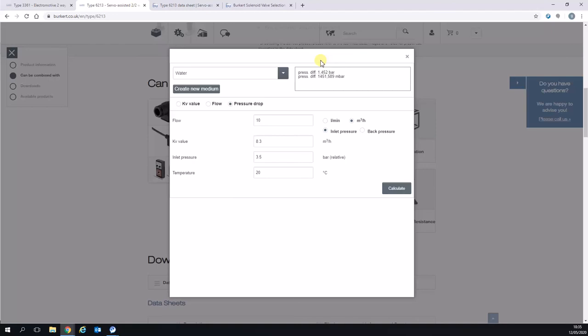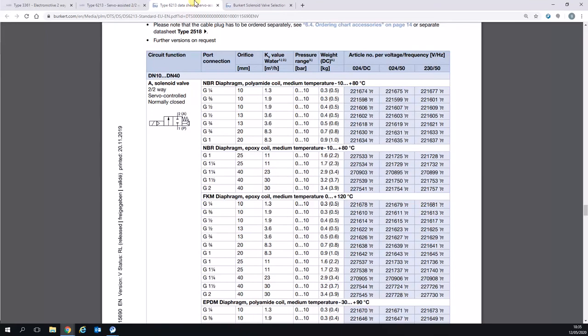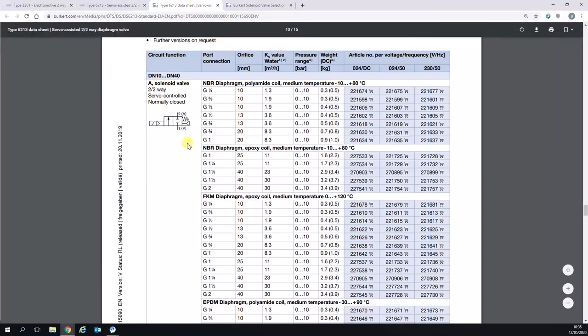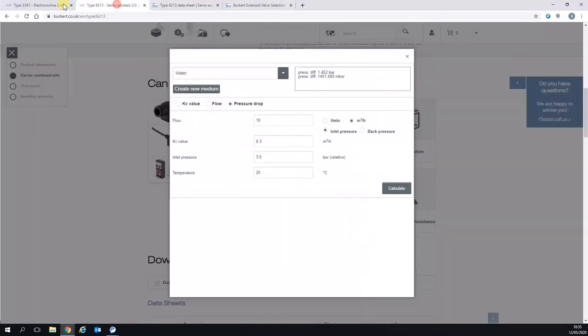You can now see that to achieve 10 meters cubed per hour with a KV of 8.3, we'd have to have almost one and a half bar pressure drop across the valve, which is quite a lot for most applications. So to achieve something more realistic, let's pick a bigger solenoid valve. For example, we pick the two inch version with a 40 millimeter orifice and a KV of 30.